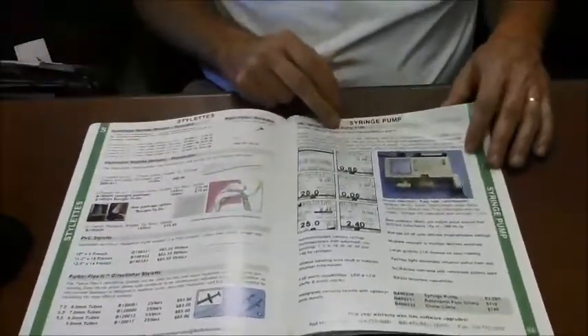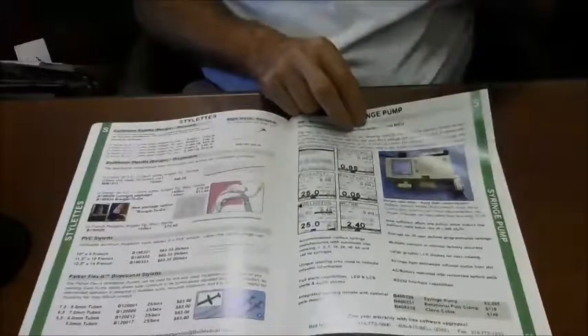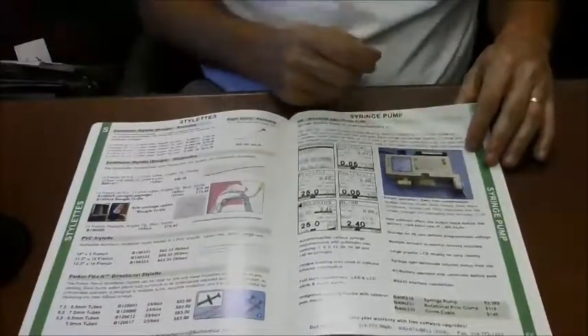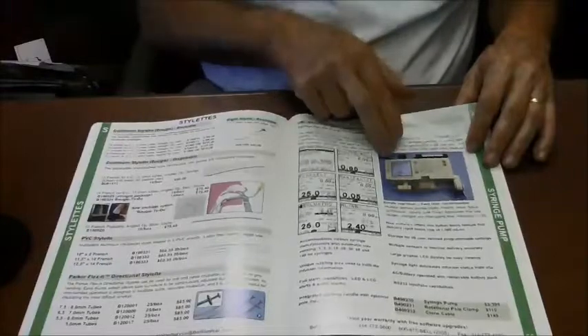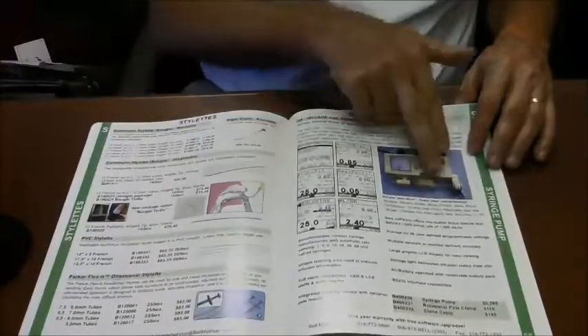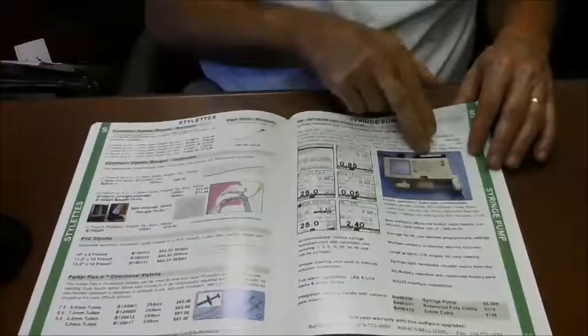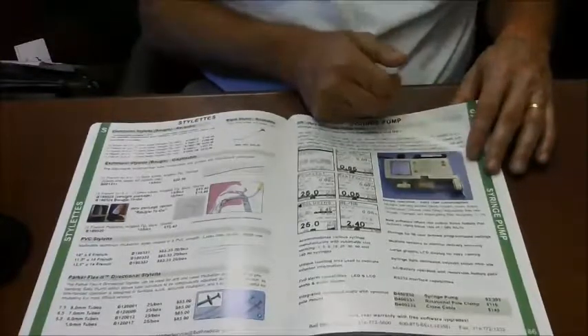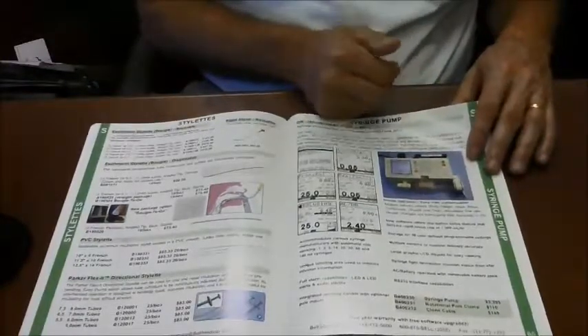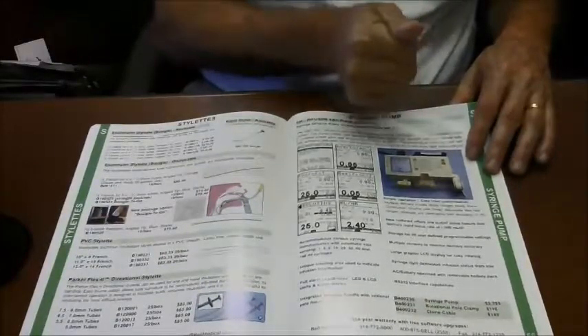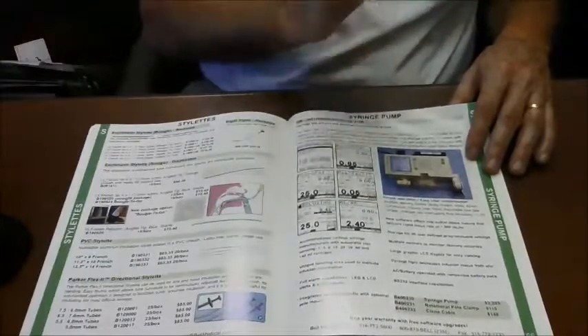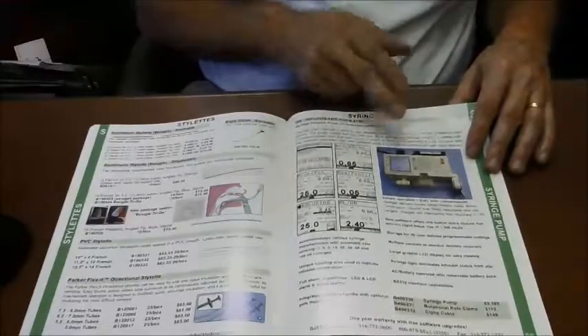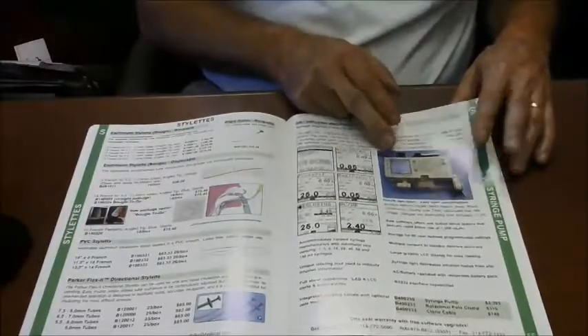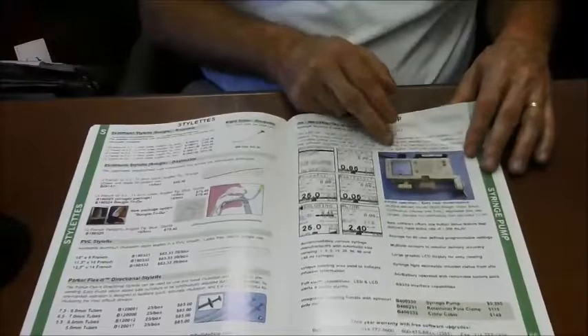Here's our syringe pump. A lot of customers are using an old style syringe pump that has a magnetic plate because it's super easy to use. This syringe pump is likewise very easy to use. It can be used in this case for propofol, and what's nice about it is anesthesia asked us to put a bolus button that gave them one button bolus pushing. So basically when you press the bolus button and then press it immediately and hold it, it will actually deliver a constant bolus while you're holding the button down. And it's super easy to use and it's very competitive. Our competition is more complicated, harder to use, and probably $1,000 more expensive.